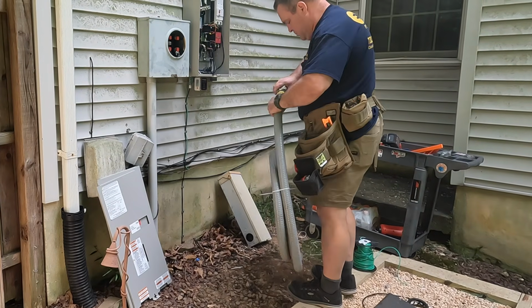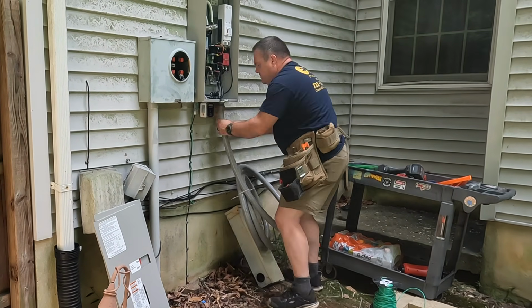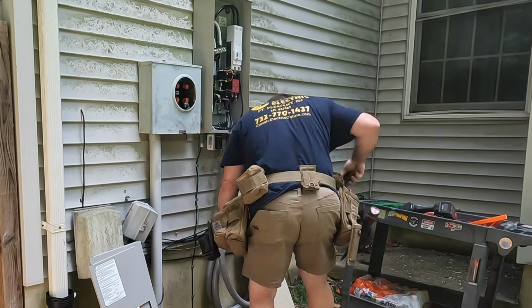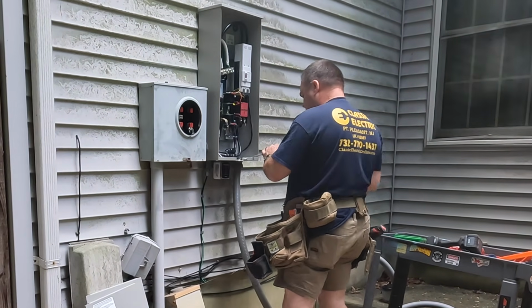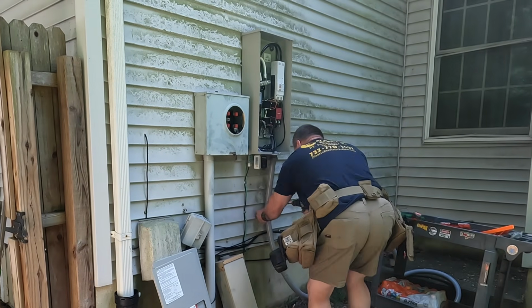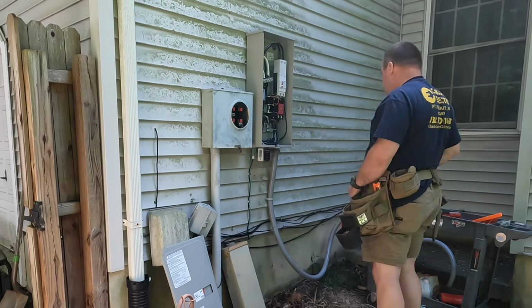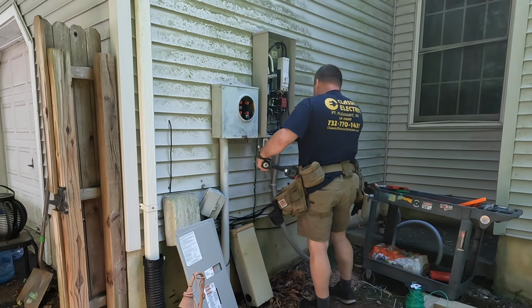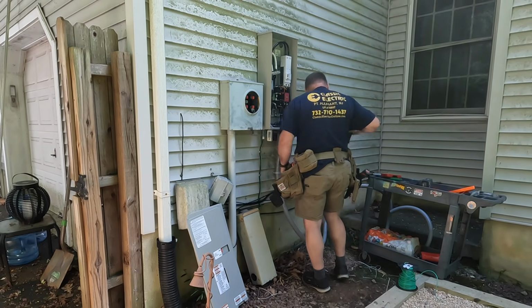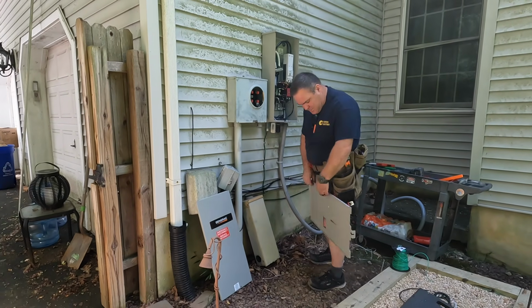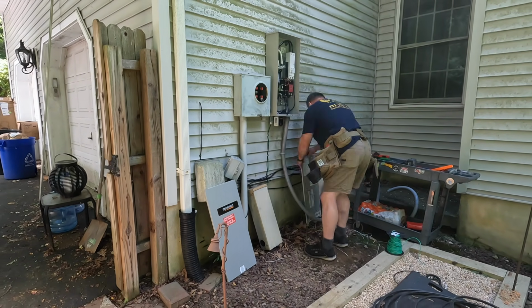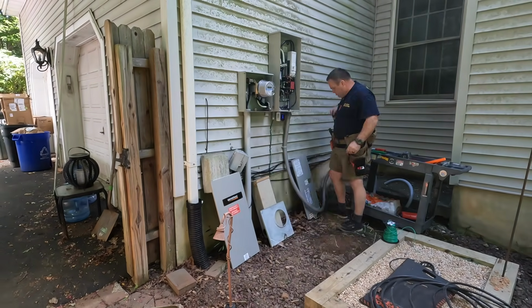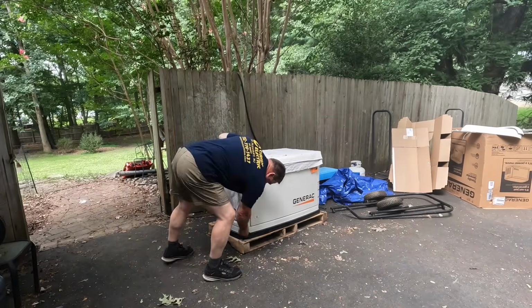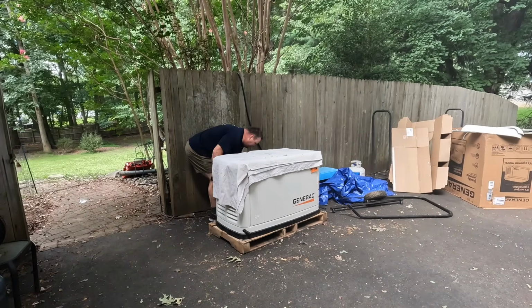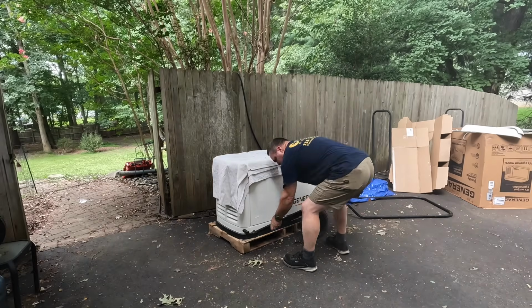This is 1.25 inch non-metallic, liquid-tight, flexible conduit, for situations where you need some flexibility. I'm going to attach it into my transfer switch and then put some straps with lag bolts, leaving the tail end until I get the generator in place. In part 2 of this video, you'll see how I wire the generator. The liquid flexible non-metallic seal tight is for flexibility and for the vibration when the generator starts up and runs. We want that connection able to move around a bit, instead of having a rigid PVC piece attached directly.